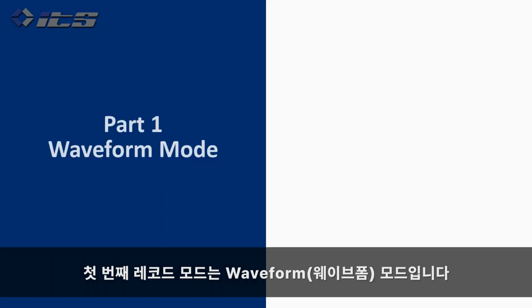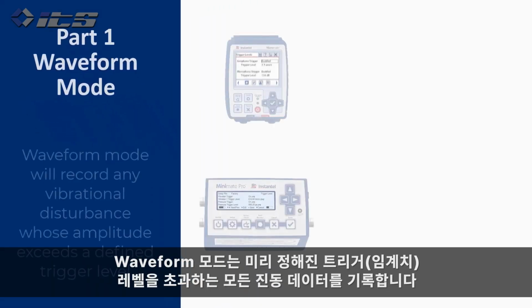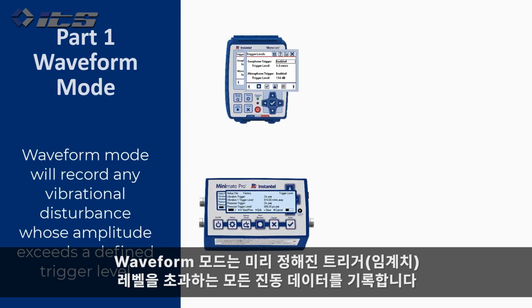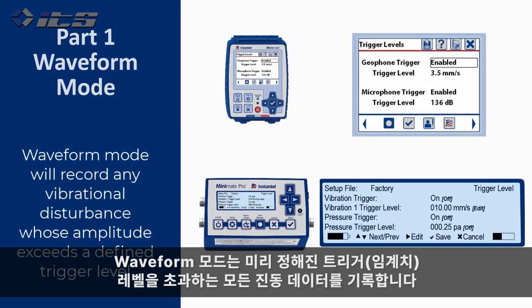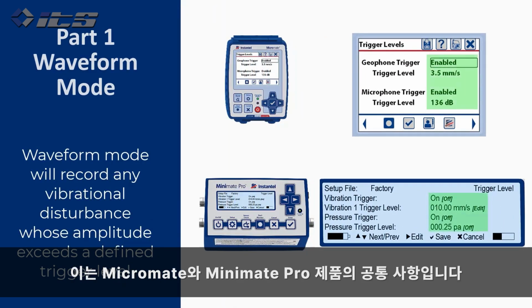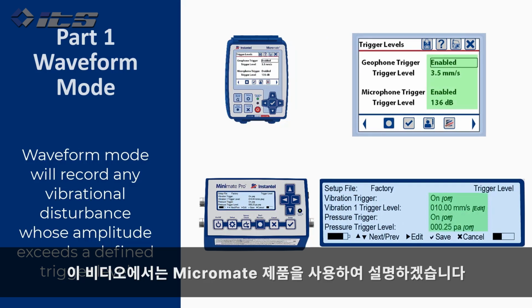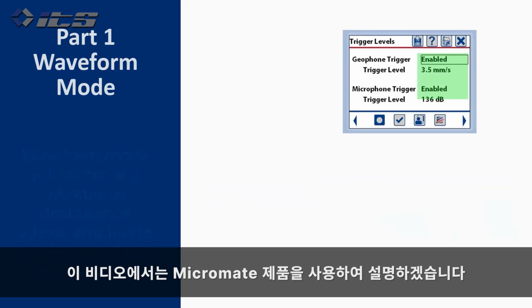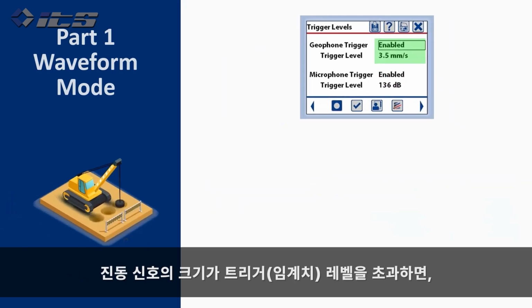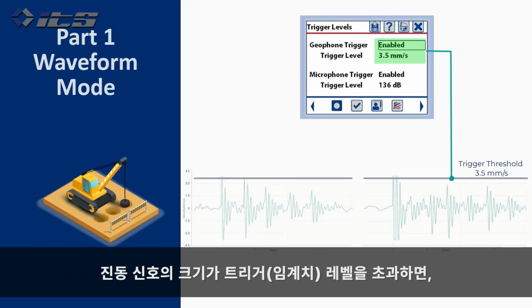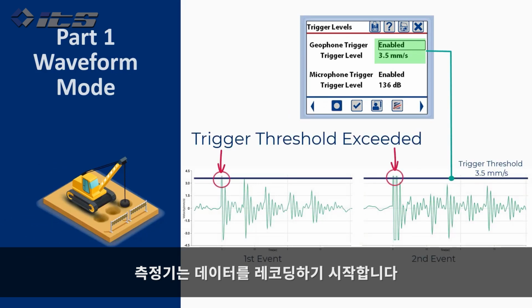The first record mode is Waveform. Waveform mode will record any vibrational disturbance whose amplitude exceeds a defined trigger level. This is true for both Micromate and Minimate units. For the sake of this video presentation, we will continue with the Micromate interface. Once one of these signals exceeds the trigger level, the unit will start recording the data.